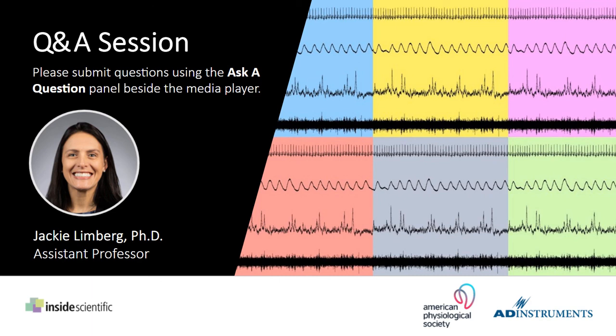And you're not going to get that 1 to 2 millisecond resolution in that signal that you really need for an accurate measure of heart rate variability. So I wouldn't recommend it. I would recommend using an ECG signal where you have a high sampling rate of about 1,000 hertz to really make sure that you have the resolution. It's just a little wavy, curvy on the top of the non-invasive blood pressure, and it's not going to give you that tight resolution that you need.